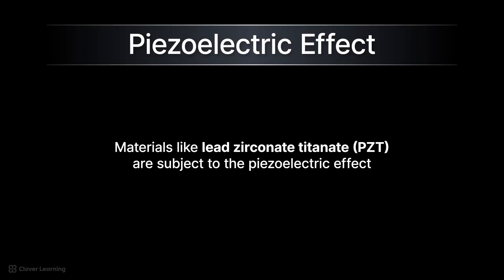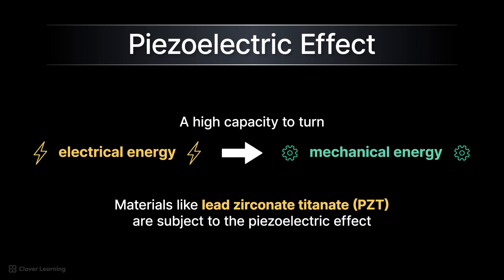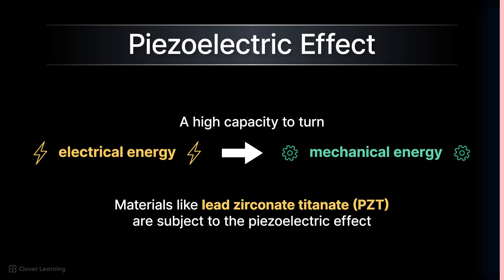It can perform this key function because the piezoelectric element is made of materials, like lead zirconate titanate, or PZT, that are subject to what is called the piezoelectric effect. This means it has a high capacity to turn electrical energy into mechanical energy, which is the energy in sound waves.